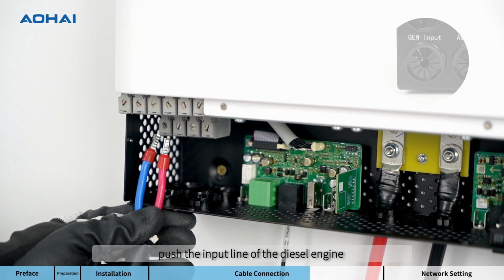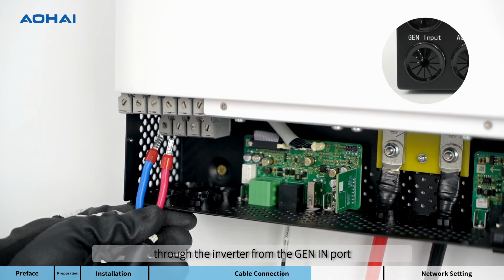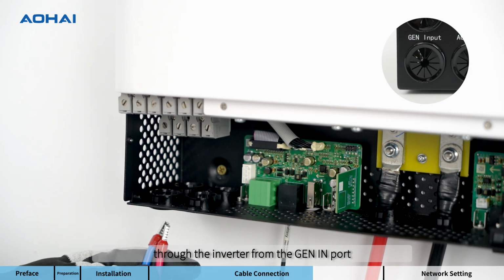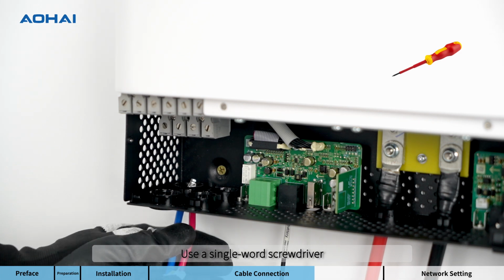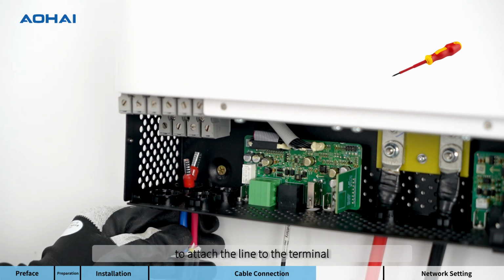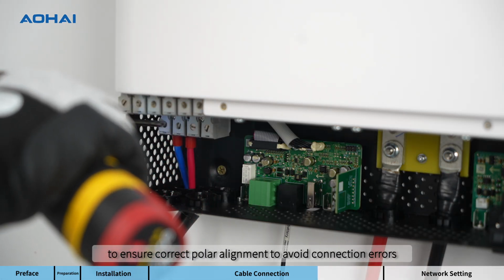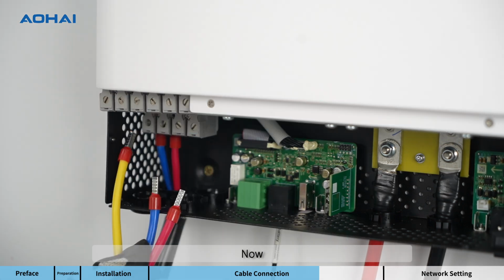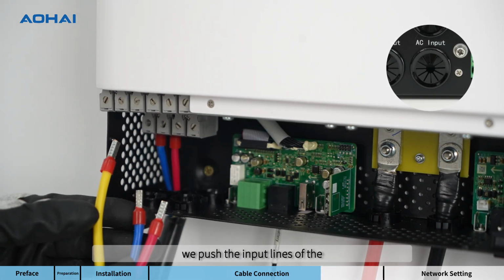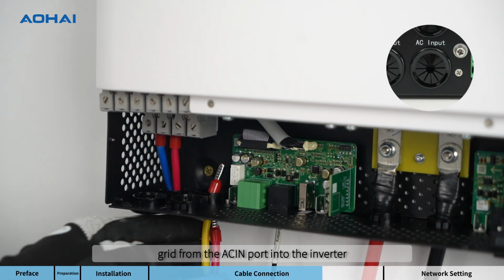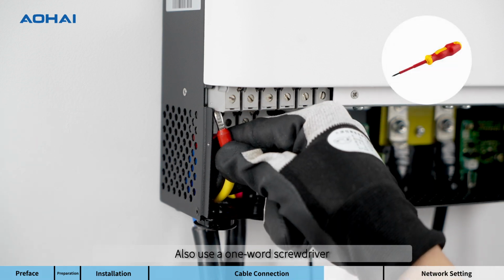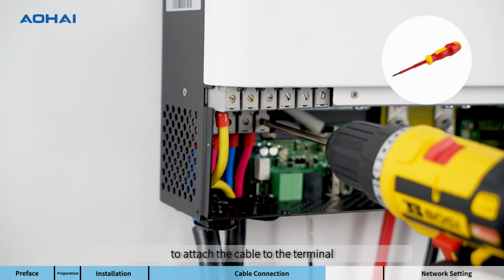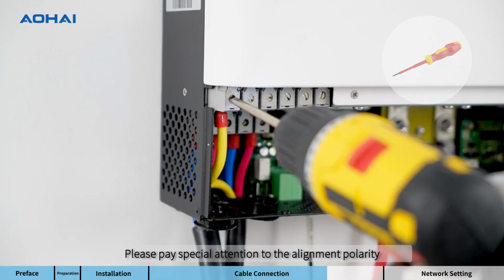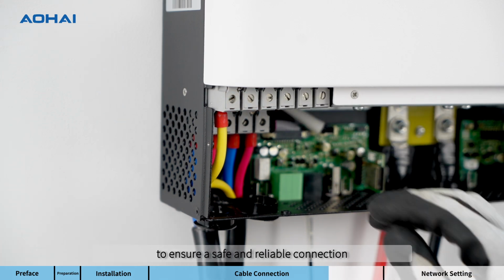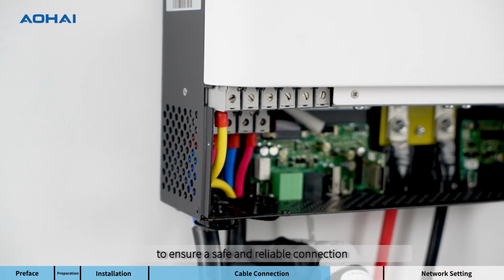Next, push the input line of the diesel engine through the inverter from the Gen in port. Use a single-slot screwdriver to attach the line to the terminal, ensuring correct polarity alignment to avoid connection errors. Now, we push the input lines of the grid from the AC in port into the inverter. Also use a single-slot screwdriver to attach the cable to the terminal. Please pay special attention to the alignment polarity to ensure a safe and reliable connection.